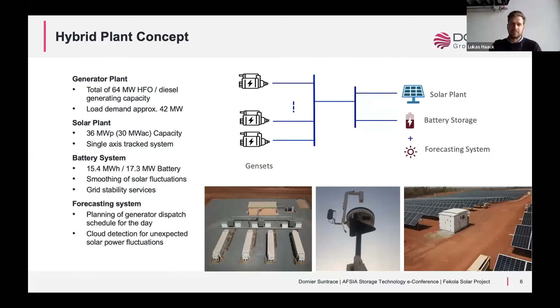The way this looks during a clear sky operation, a typical day, is that with the start of solar power production you ramp down some of the engines and then ultimately switch off engines one by one till you reach generation at 3 engines. During a clear sky day, the system allows you to switch off all engines except for 3, and then ramp down those engines to allow up to 75% of the power to be provided from solar.